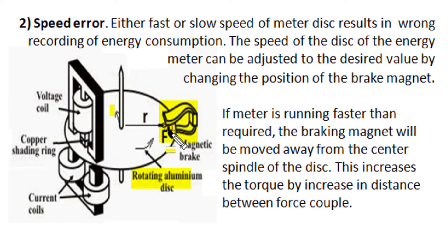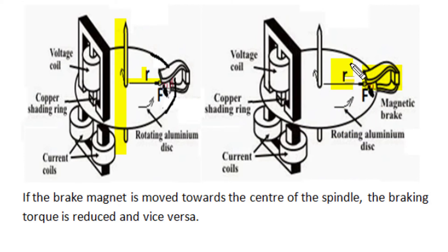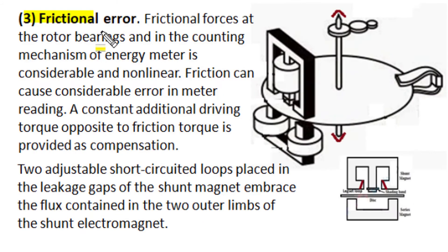The braking torque is equal to the product of force and the radial perpendicular distance between the spindle axis and the brake magnet position. If a meter is running faster than required, we move the brake magnet away from the central spindle axis — this increases the radial distance, increases braking torque, and reduces speed to the desired level for accurate measurement. When the brake magnet is moved closer to the spindle, the radial distance decreases, braking torque reduces, and the disk rotates at a faster speed.